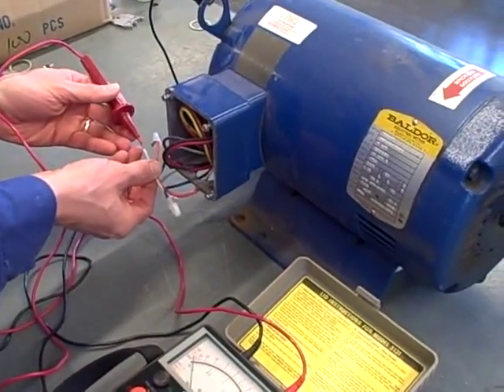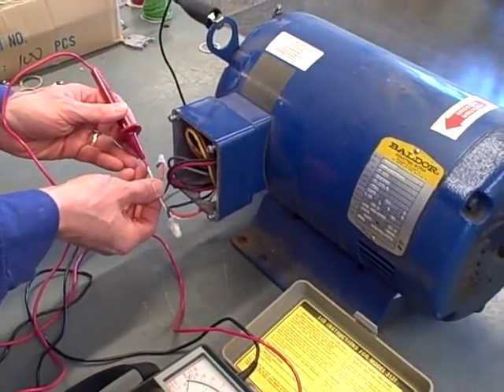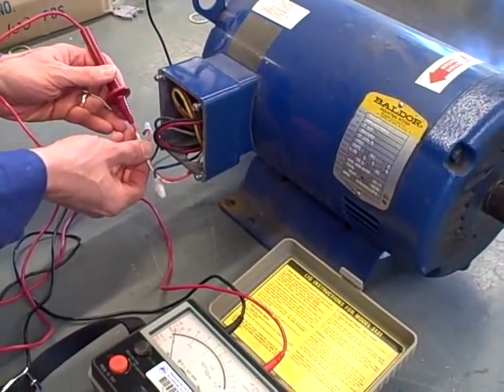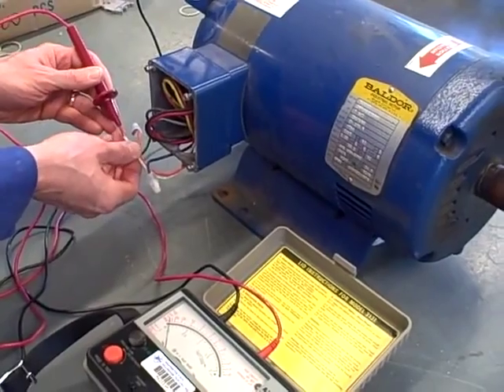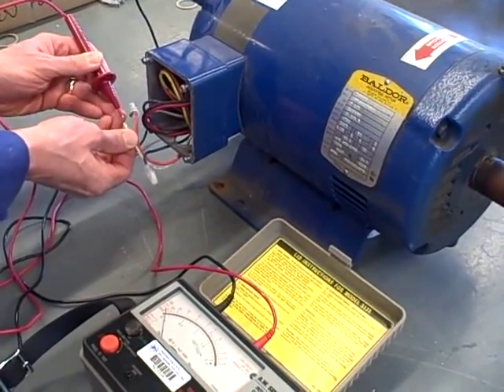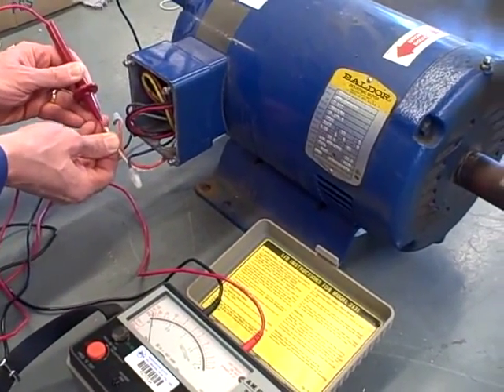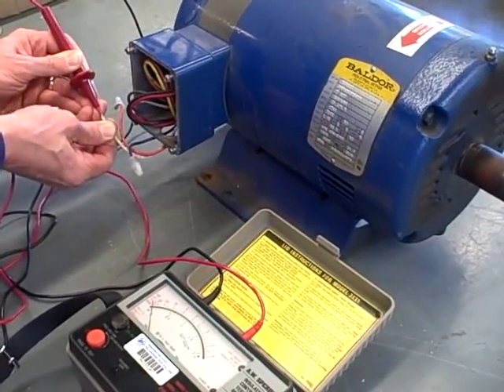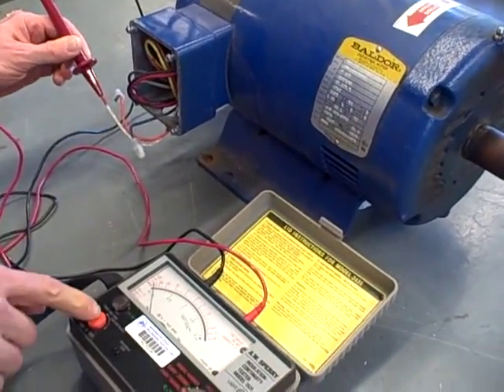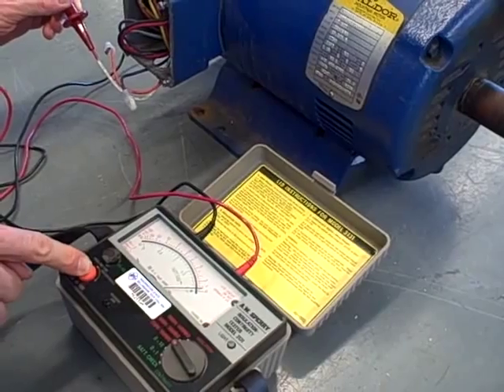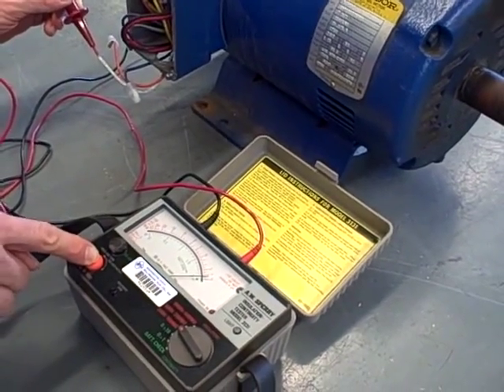I'm going to make my connection between my test probe and the bare end of the wire as such, and then when I make that connection, holding that with one hand, I'm going to reach over with my other hand and push the orange button on the Megger tester to actually energize it. So here's my connection being made. There's the button, and notice how the needle swings over all the way to the right.